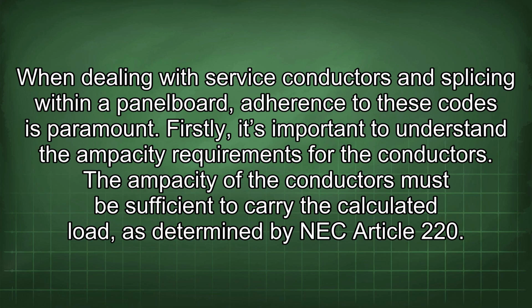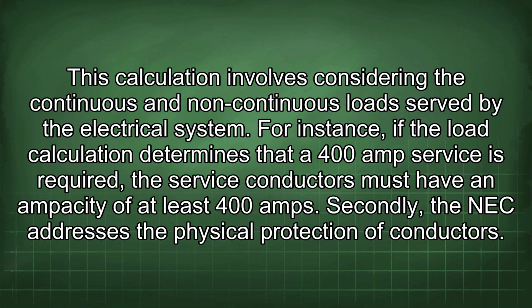Firstly, it's important to understand the ampacity requirements for the conductors. The ampacity of the conductors must be sufficient to carry the calculated load, as determined by NEC Article 220. This calculation involves considering the continuous and non-continuous loads served by the electrical system. For instance, if the load calculation determines that a 400 amp service is required, the service conductors must have an ampacity of at least 400 amps.